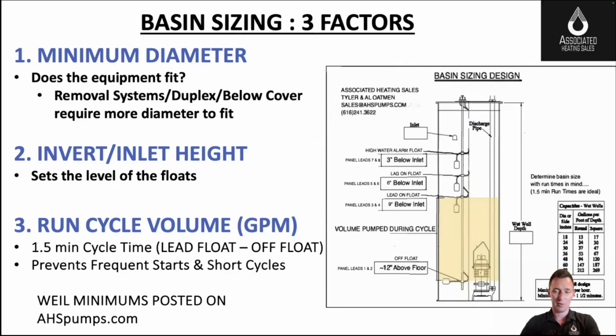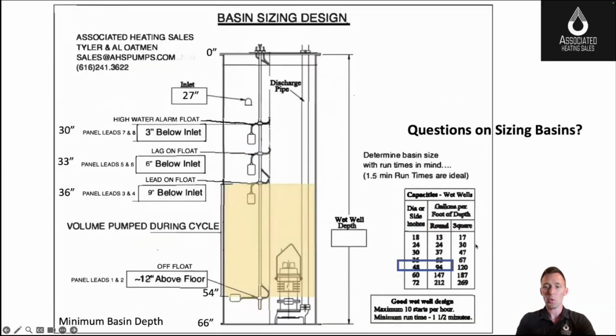If we can get the pump to run for a minute and a half or 2 minutes, Weil says, hey, that's no longer short cycling the pump, and that's an appropriate runtime. So just to do some easy math, every Weil cut sheet has how many gallons are in each foot of a certain diameter basin. In this case, I have a pump doing 100 gallons a minute. I'm in a 4-foot wide basin. So I've made this really easy. It's about 100 gallons per foot. So I need 1.5 feet of distance between the on and the off float.